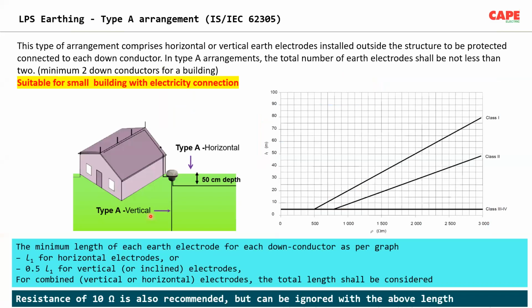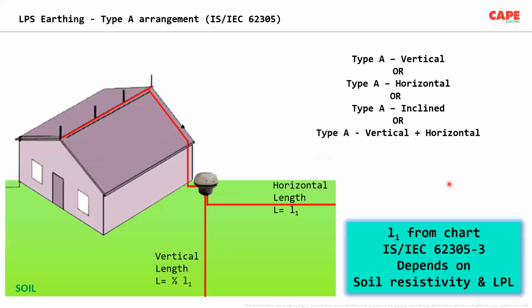Now, the only application where you need a specific value of earth electrode resistance in a low voltage or an industrial consumer premise is if you go for an earth electrode in soil, especially a type A earth electrode in soil. Then people ask, what is this type A earth electrode? Type A earth electrode means, as you can see in this particular picture, there is a building, there is one down conductor. Sorry, maybe on the other side there is one more. Every building should have a minimum of 2 down conductors. Each down conductor is connected to an earth electrode in soil, and these earth electrodes are either vertical or horizontal. Now, in soil, there are some calculations given in the standard. You have to put a certain length X of the earth electrode in soil, and if you cannot put that particular length X, you are supposed to make the resistance lesser than 10 ohm. So something like this, a vertical or a horizontal length.